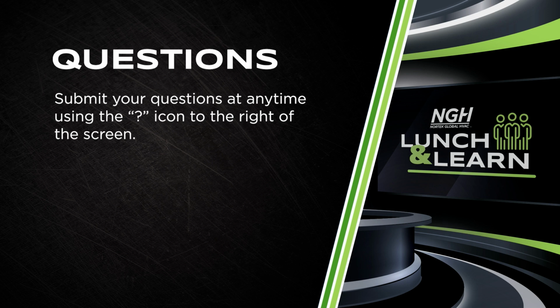Really good question. So anything that is electromechanical that's interacting with the refrigerant, like a vacuum pump, you're going to want to make sure that it is A2L rated. To do that, you're really contacting the manufacturer of that device and making sure they're saying it's okay for that. For more passive things like hoses and gauges, those won't necessarily carry an A2L cert, but we don't want to cross-contaminate refrigerants. So you're probably going to want a separate set of hoses and gauges for 410A and for 454B, and maybe 32 potentially if you're into that as well.